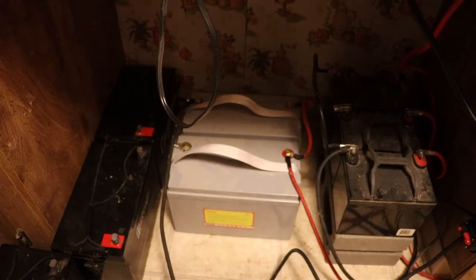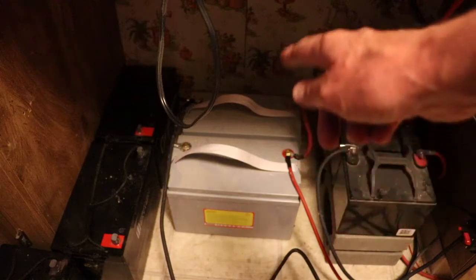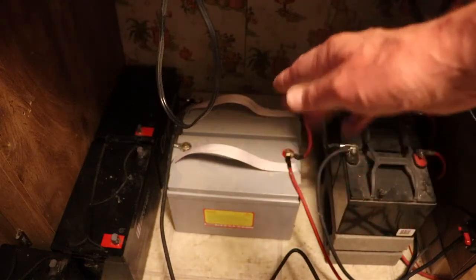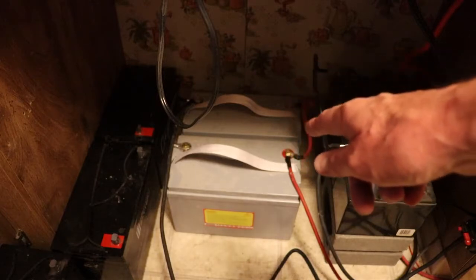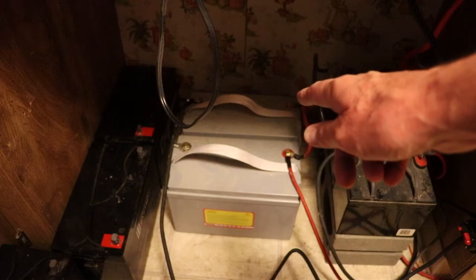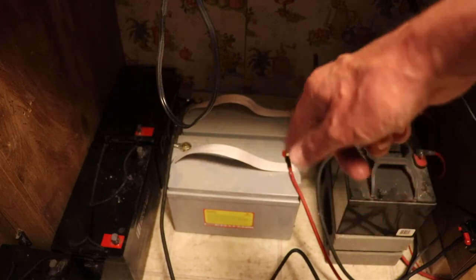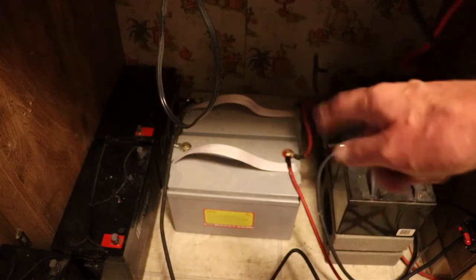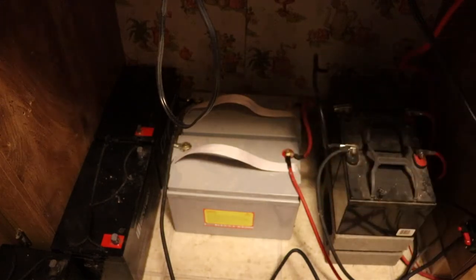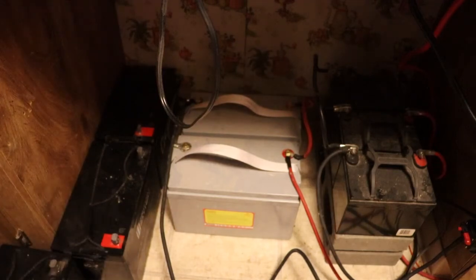And also be careful with these lithium-ion batteries. Not all BMSs that equalize the voltage are the same. Some of them will tell you can't put these batteries in series. Sometimes they'll tell you can put 2 in series. This one you can put 2 in series. And the ones I bought for the new updated system, you can put 4 in series, so I can get a nice 48 volt DC system when I go for a different system. The higher up you go in voltage, the more efficient your power is going to be, and it's going to charge a lot faster. So at 12 volts it's really not the most efficient. 24 is better. 48 volts DC for the battery system is the best.